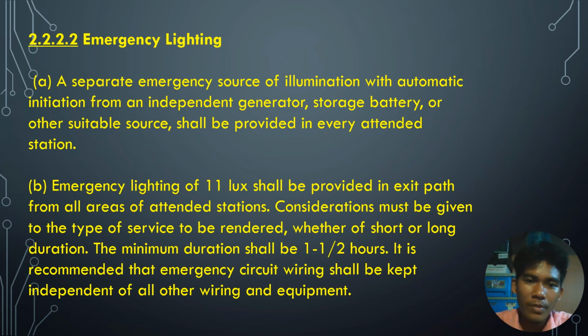Emergency lighting. A separate emergency source of illumination with automatic initiation from an independent generator, storage battery, or other suitable source shall be provided in every attended station. Emergency lighting of 11 lux shall be provided in exit paths from all areas of attended stations. Consideration must be given to the type of service to be rendered, whether of short or long duration. The minimum duration shall be 1 1/2 hours. It is recommended that emergency circuit wiring be kept independent of all other wiring and equipment.